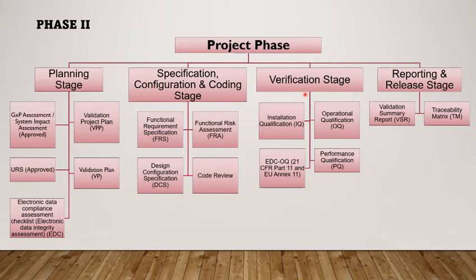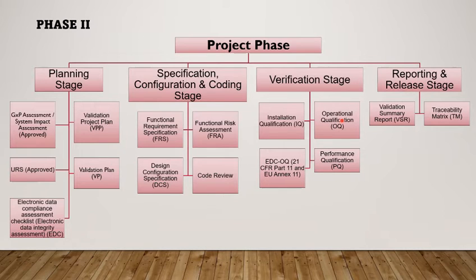The third stage is the verification stage. It covers thorough testing of the system using predefined test scripts and approved validation protocols. Qualification testing shall cover all the requirements stated in the URS and FRS. Installation qualification should confirm that the required physical hardware and software have been installed and configured correctly. Operational qualification should confirm the system operates according to its written and pre-approved specifications, covering verification of report requirements, backup, registration, user roles and privileges. Electronic data compliance OQ verifies system compliance with 21 CFR Part 11 and EU Annex 11 regulation. Performance qualification should confirm the verification of business processes, that is the end user requirements.